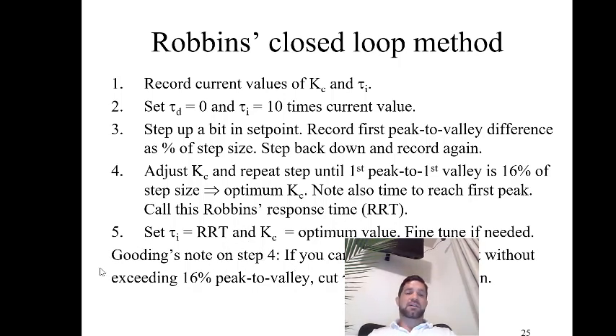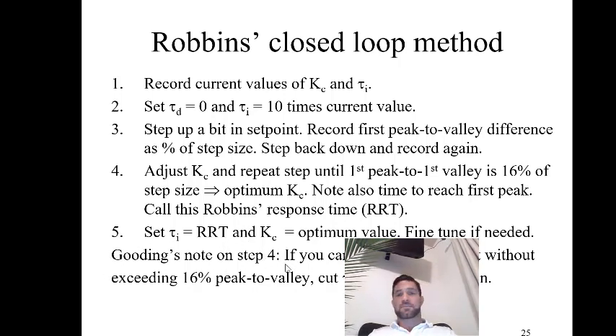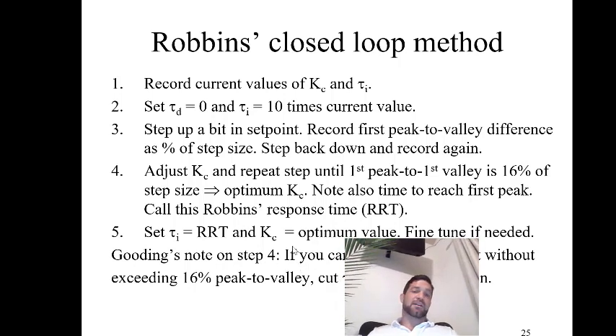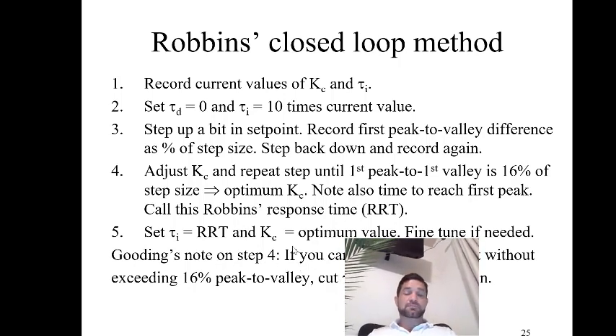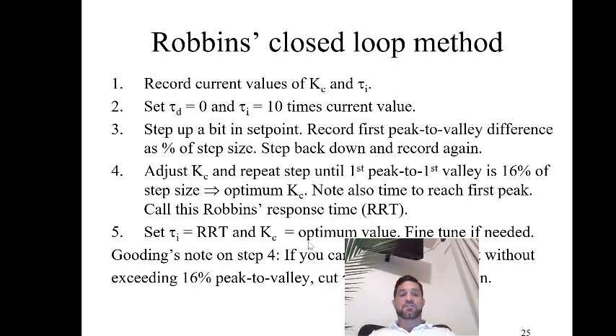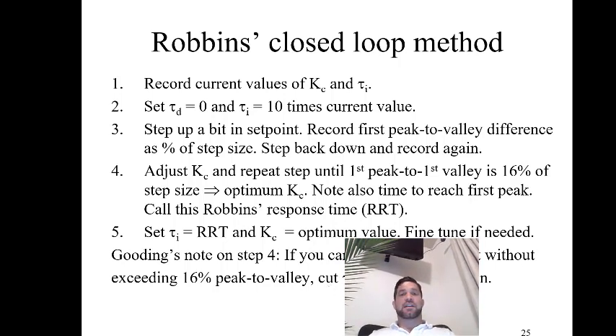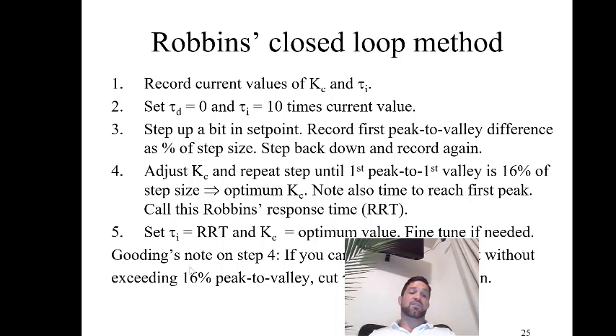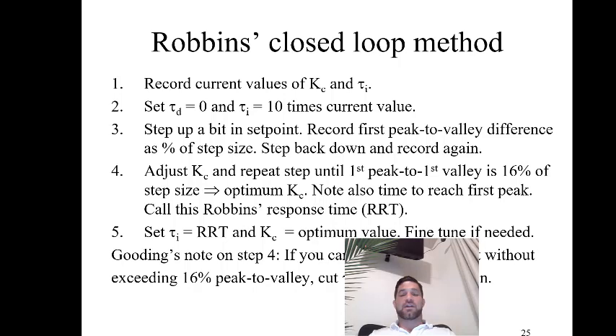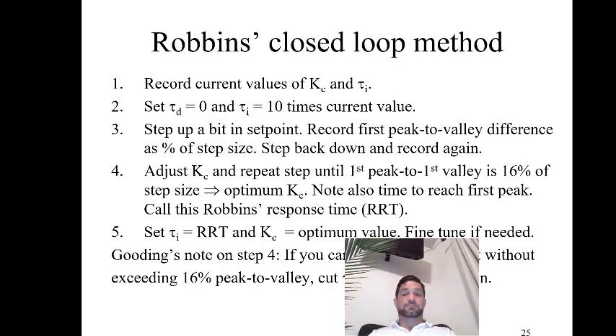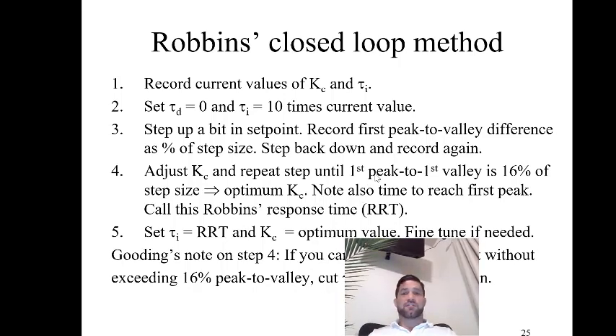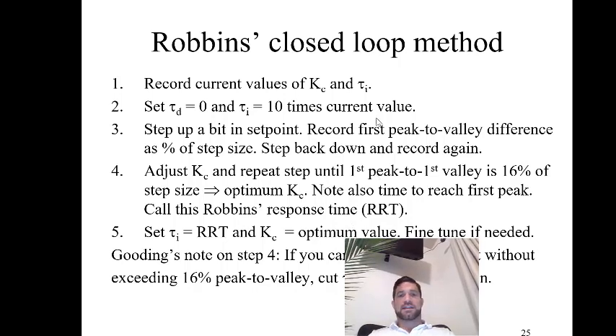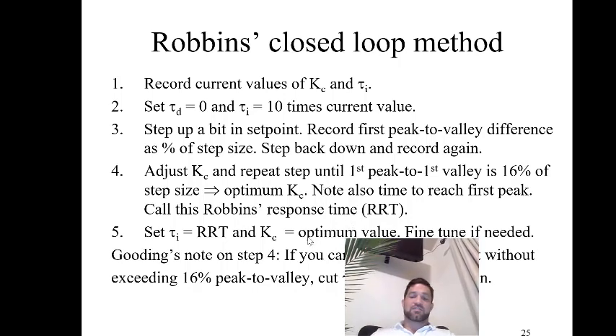Now a specific note that was provided by Dr. Gooding, who used to teach this class but is now retired. He says if you can't get any overshoot without exceeding 16% peak to valley, cut the τI in half and try again. If you can't ever get any overshoot, then you just need to go along with 16% with τI turned off. Record the time and that should give you a first guess. You might have to tinker a little bit with the values of KC and τI, but it'll get you close to what you need.